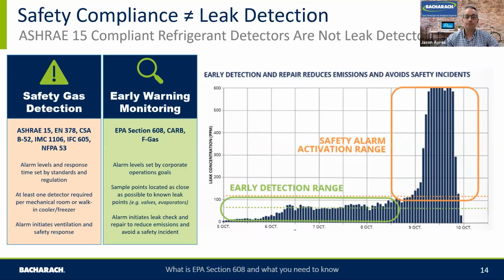The other side is leak detection. This is turning the sorts of leaks on their head. The technologies available now can go much lower in the detection range of picking up refrigerant in the air. Ranges from 1 to 100 parts per million is what we term early leak detection, early warning to potential large refrigerant losses. If you look and respond to leaks in that range, you will reduce your refrigerant usage. You won't eliminate it completely, but you'll certainly help reduce your refrigerant loss, find more leaks, find more small leaks, and help your overall leak detection strategy.